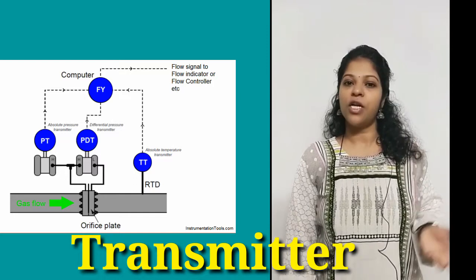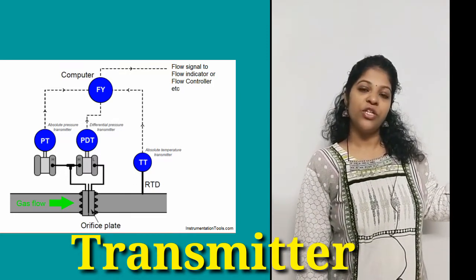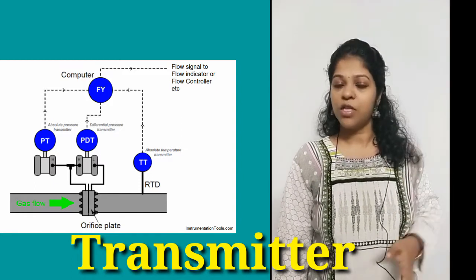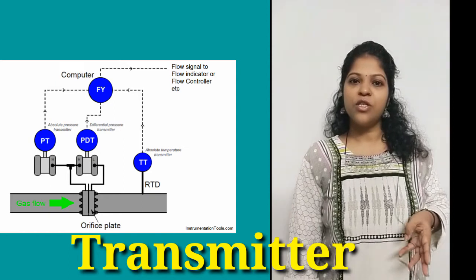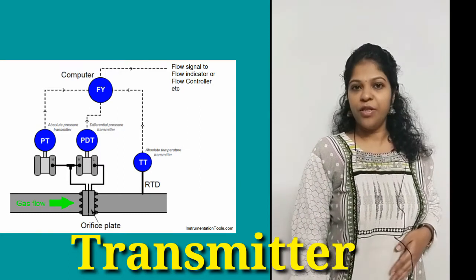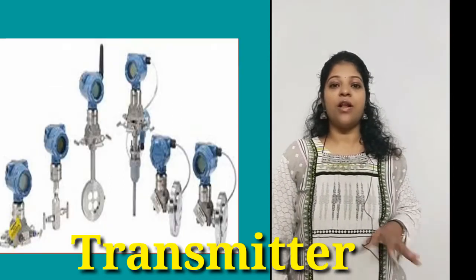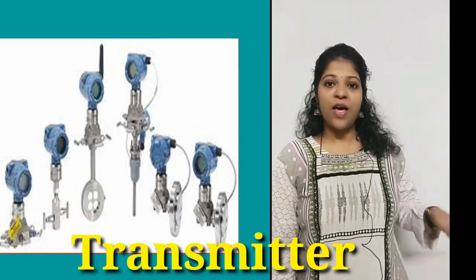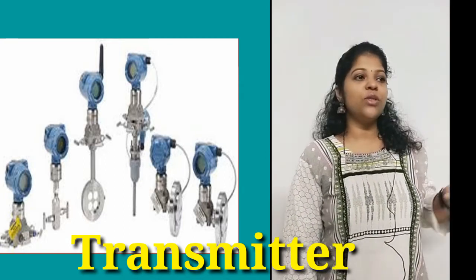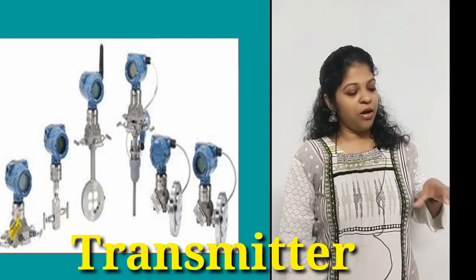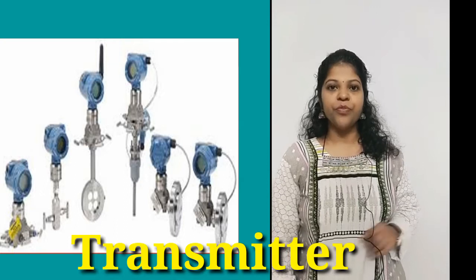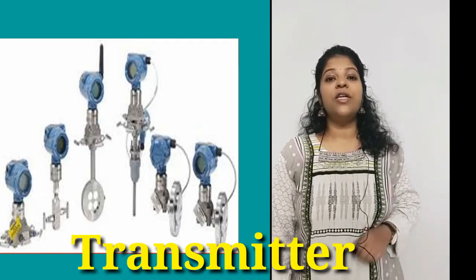The control room is at a remote location. To transmit a signal to it in order to control the plant, a strong transmitter is needed. These transmitters are named based on the process variable — a temperature transmitter is called TT, a pressure transmitter is called PT. As shown in the diagram, there are wireless transmitters and head-mounted transmitters. The head-mounted transmitter senses and transmits at the same point — the transmitter circuit is attached directly on the sensor head — transmitting a 4 to 20 milliampere signal.